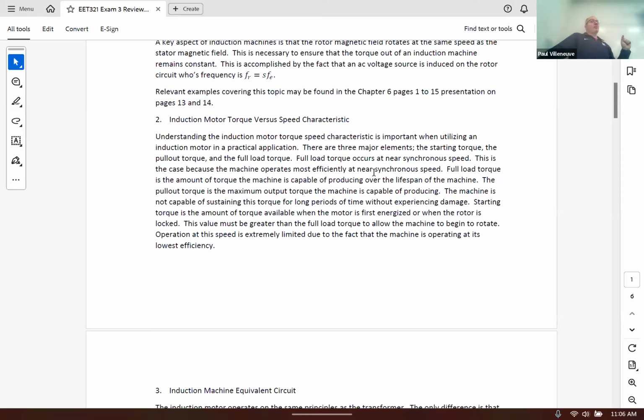Just because the induction motor is rated to produce, let's say, 100 horsepower or 200 horsepower, that doesn't mean it has to operate at 200 horsepower. If the mechanical load is less than the 200 horsepower, that motor is going to speed up until it matches whatever the mechanical load demands from it. Just because it is capable of providing 200 horsepower doesn't mean it's actually providing 200 horsepower. Again, it's all based on the load. The mechanical load is what's going to dictate the speed of operation.